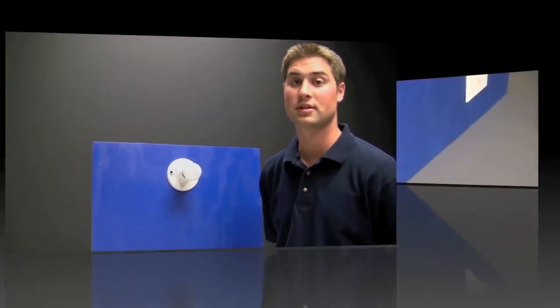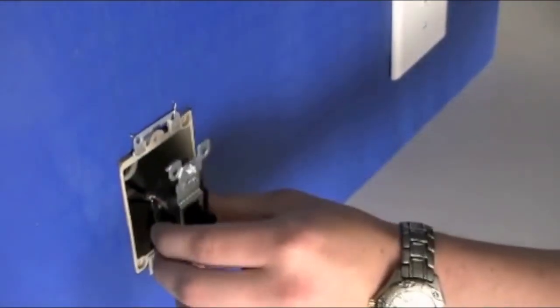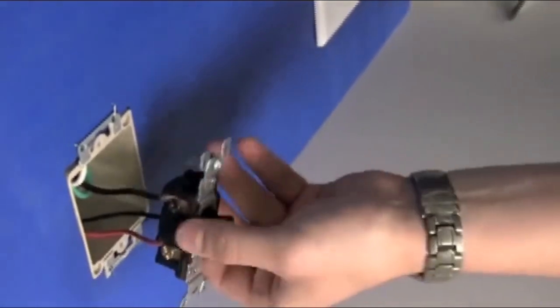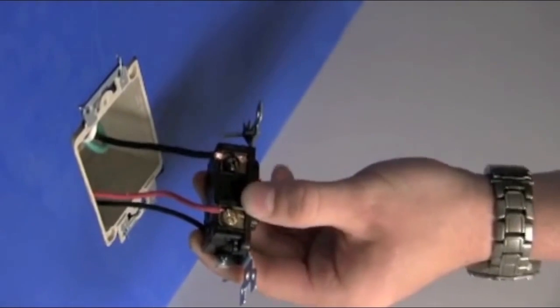Now that we've covered those topics let's get started with installing the timer. We're going to need to locate the common wire on our three-way switch. To find the common wire remove the switch from the wall and locate the odd colored screw. That will be the common wire.